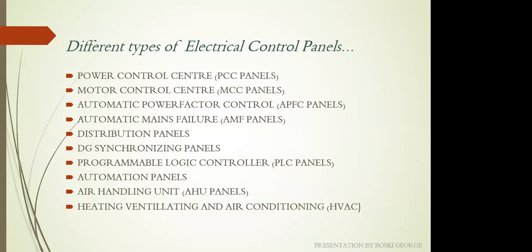Next is the AMF panels, auto mains panels, relay panels, used in diesel generators. If the electricity board's power fails, it will automatically switch on the DG, and when the electricity board's power comes back, it will automatically shut down the DG. So for that we need a panel that switches the DG on and off automatically. This panel is called AMF panel, and distribution panels are there too.